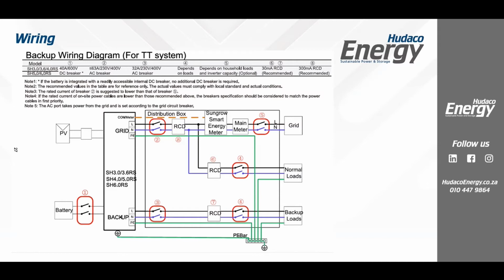If you're not doing it, start doing it, because it just gives them the option to go that way, or to really earth the system properly from a safety perspective. But I'm going to talk about the TT for now. We do supply in the manual all 3 wiring diagrams, by the way. Just please have a look on the site. What we've also found is that the same installer might do an identical installation on 2 separate homes, and the one we have to put an earth neutral bridge in, and the other one we have to take it out. And again, it really just depends on what's happening from the municipal connection side. Okay, so please just be aware and take a look.